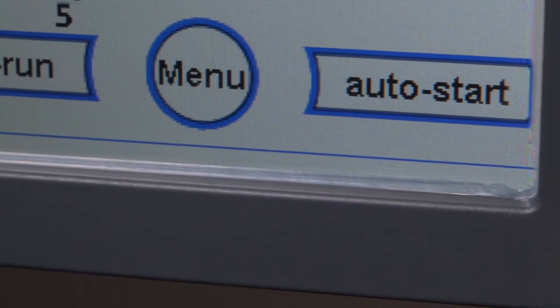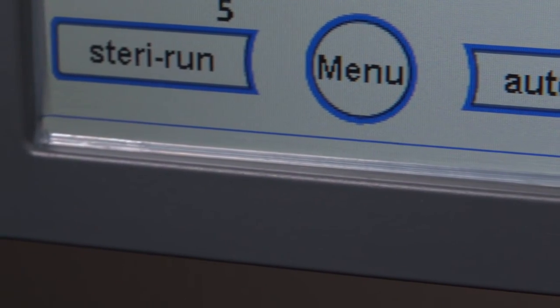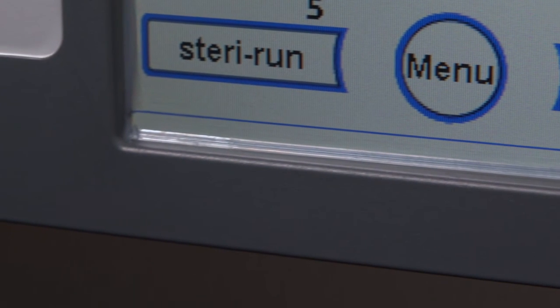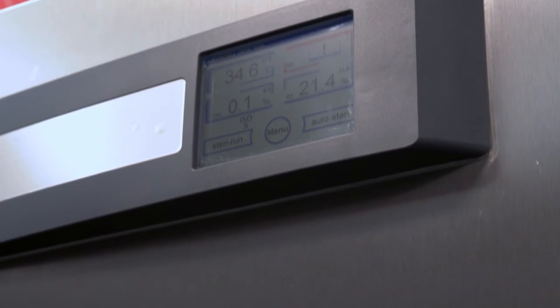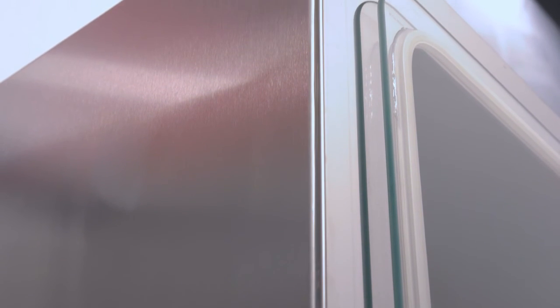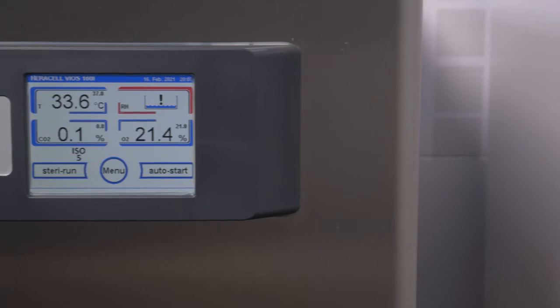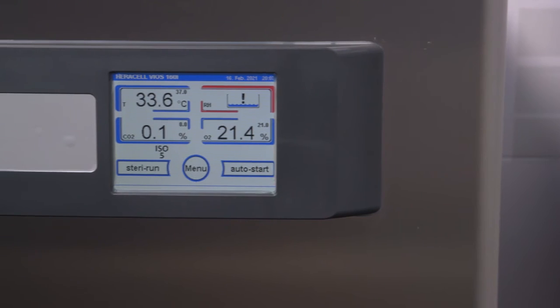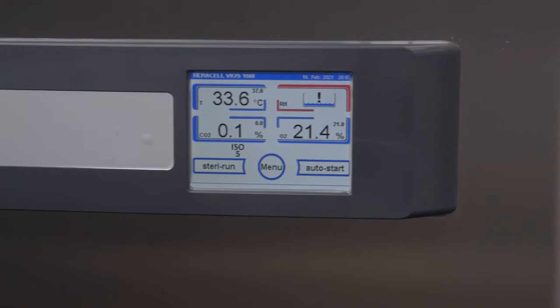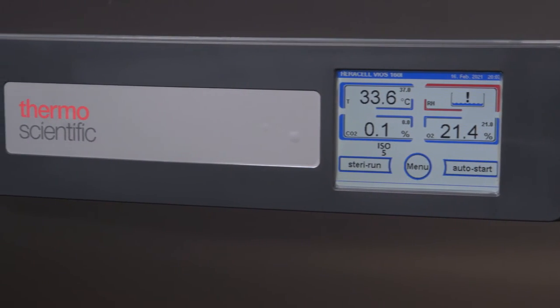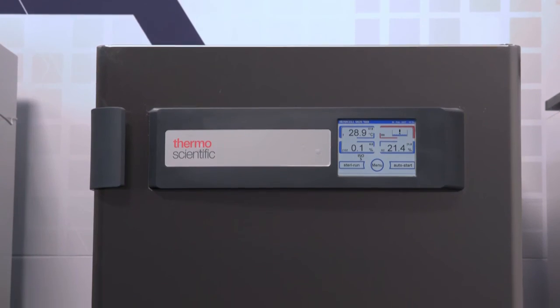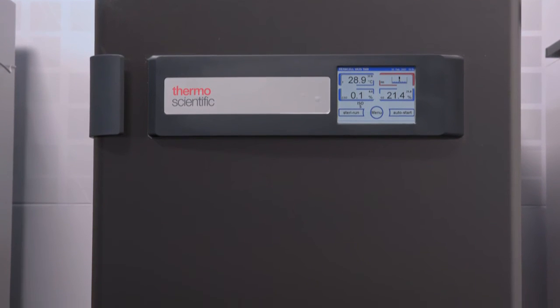We've also sealed the front bezel and the iCAN touch screen. So this is really a two part solution. One is that it's containing any particles so that they're not escaping outside of the particle control system. But also it's protecting the electronics and the touch screen to make sure that they're impervious to the cleaning methods such as VHP or any kind of hydrogen peroxide cleaning method.